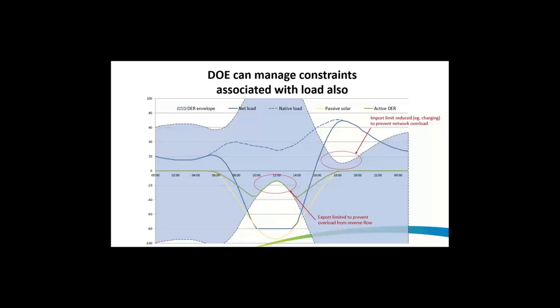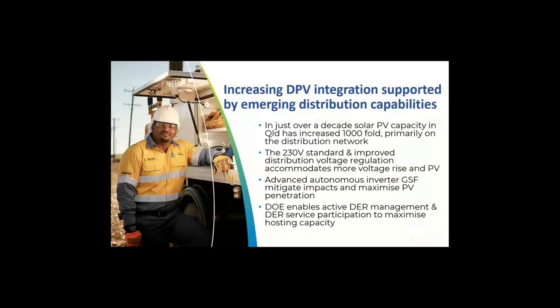In summary, increasing distributed PV integration has been supported by emerging distribution capabilities in our network. In just over a decade, solar PV capacity in Queensland has increased 1,000-fold, primarily on the distribution network. The 230-volt standard and improved distribution voltage regulation accommodates more voltage rise and PV. Advanced autonomous inverter grid support functions mitigate impacts and maximize PV penetration. And dynamic operating envelopes will enable active DER management and DER service participation to maximize hosting capacity.